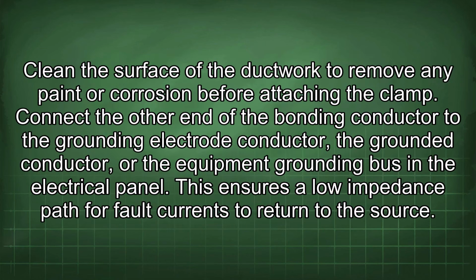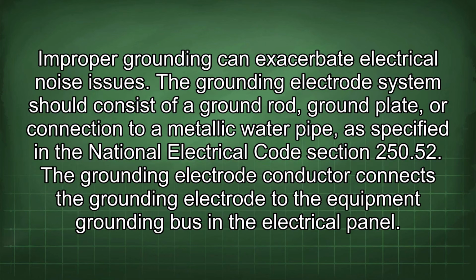Clean the surface of the ductwork to remove any paint or corrosion before attaching the clamp. Connect the other end of the bonding conductor to the grounding electrode conductor, the grounded conductor, or the equipment grounding bus in the electrical panel. This ensures a low impedance path for fault currents to return to the source. Improper grounding can exacerbate electrical noise issues.